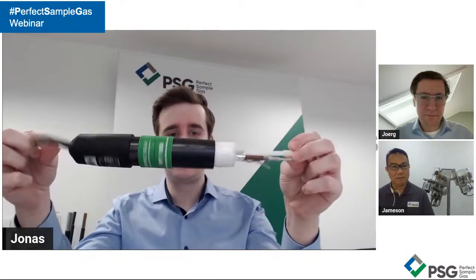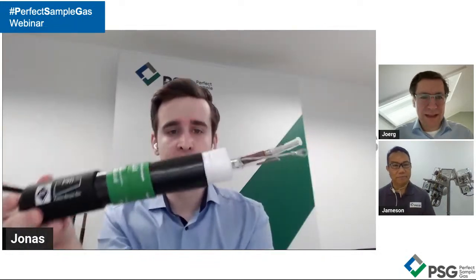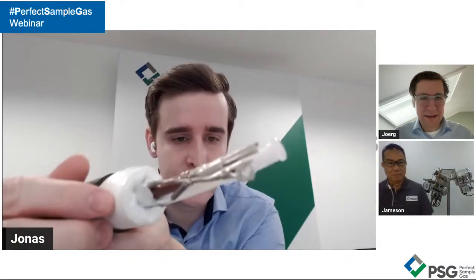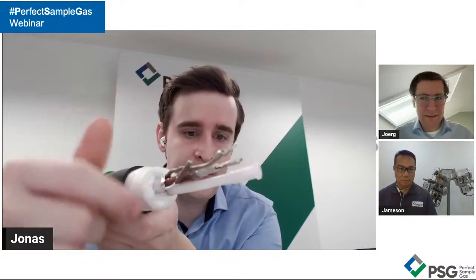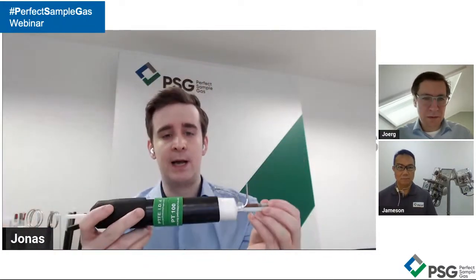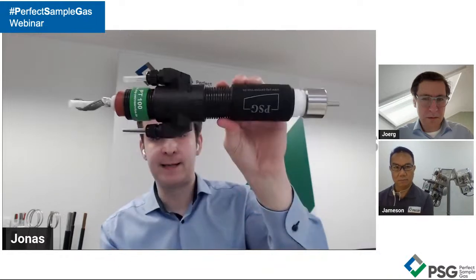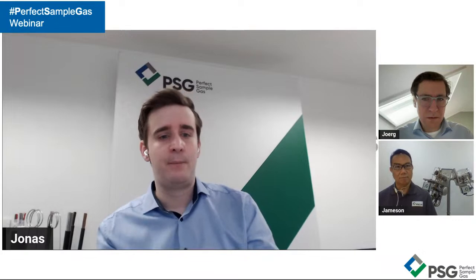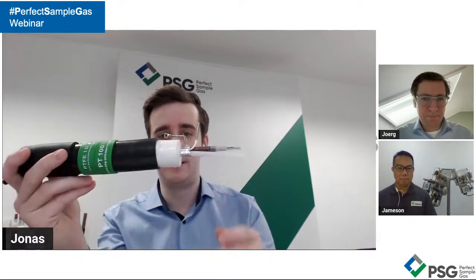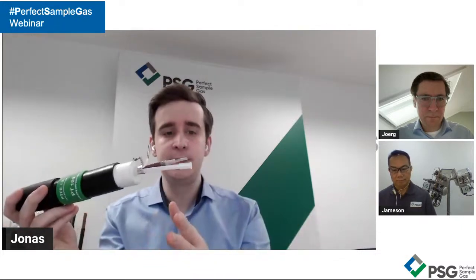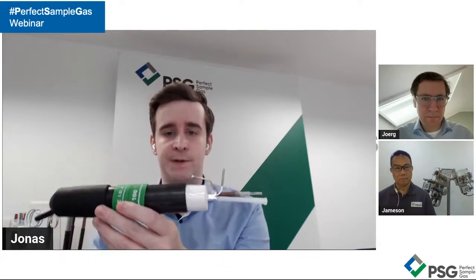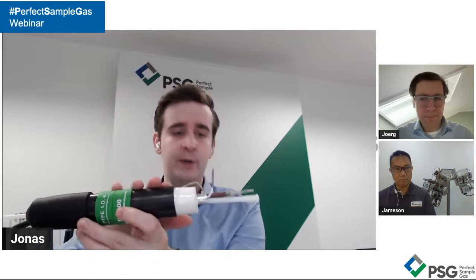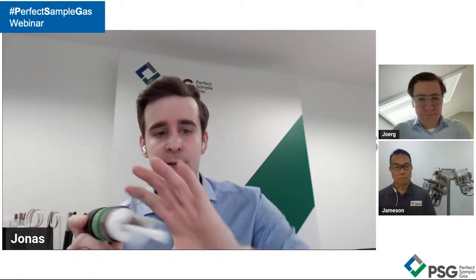We talked a lot about this little guy here. This is one of our PSG Basic extruded lines. It contains the same elements you can see here: a tube, in this case a PTFE tube, a temperature sensor, and a heating cable. The heating cable in these extruded lines is a bit different - we use a parallel heating cable, which has the big advantage that you can cut it to length every half a meter. So you can do the same as you would with the flex line - order about 10 meters extra to be safe, then cut it to the exact length your probe requires, which leads to a shorter T90 time and also lower energy consumption.